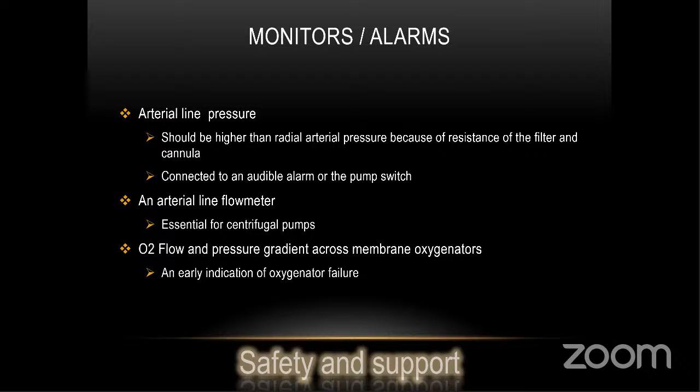In-line oxygen flow and pressure gradient across the membrane oxygenator should be continuously monitored, as any disturbance could be an early indication of oxygenator failure.